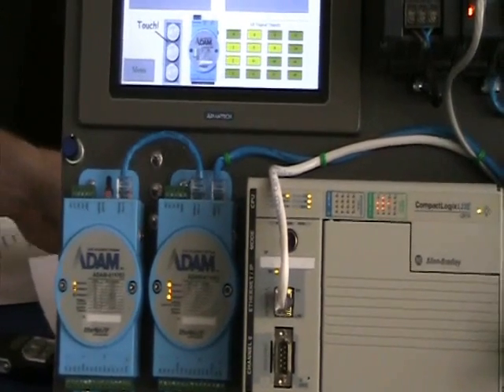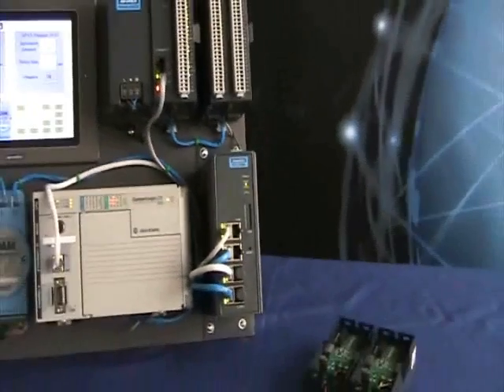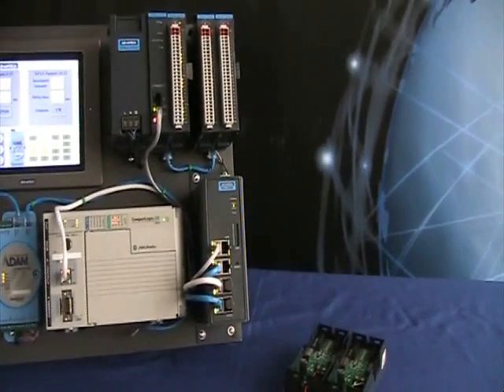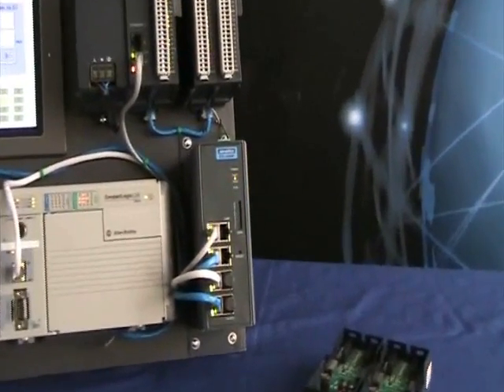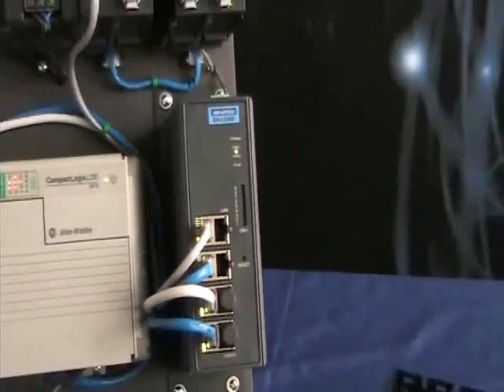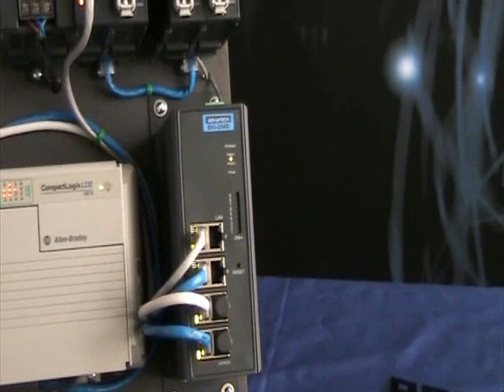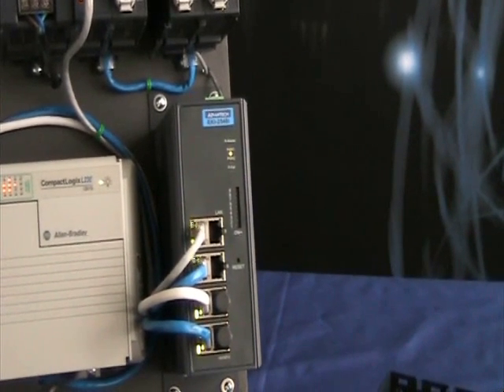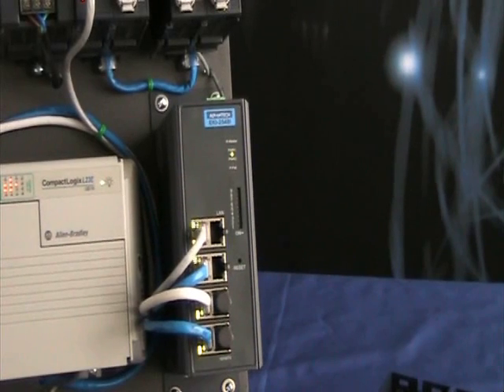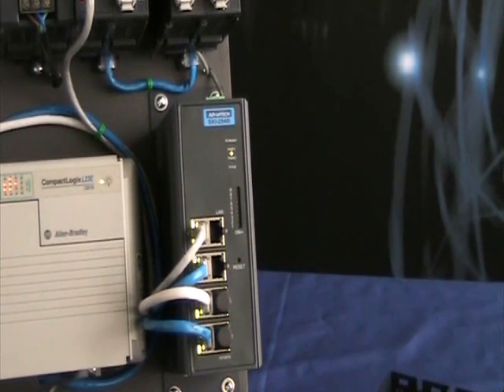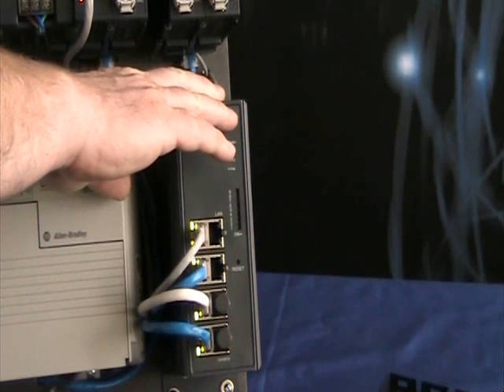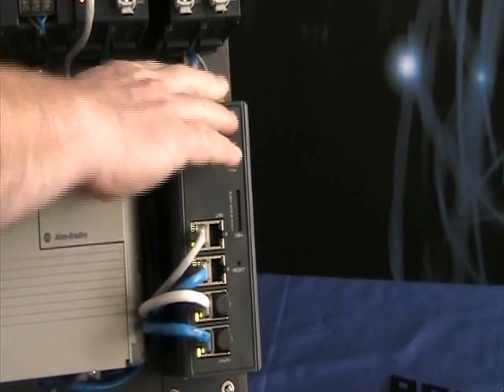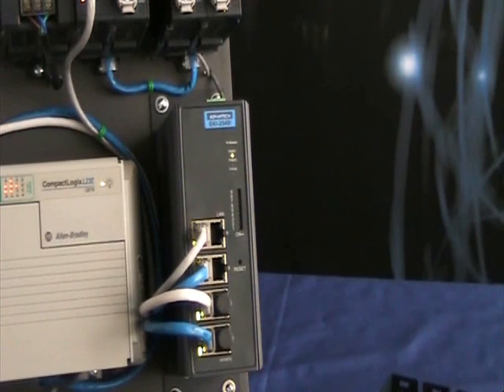And finally, we have all of this tied together with this industrial Ethernet switch. This is the EKI-2548i, which is an 8-port managed Ethernet switch with wide temperature range from minus 40 to 75 degrees C. It offers great redundancy capability with X-ring, dual homing, coupler ring, and RSTP STP. It has a redundant power input, so there's two 12 to 48 volt power inputs, and then it also has one relay output.